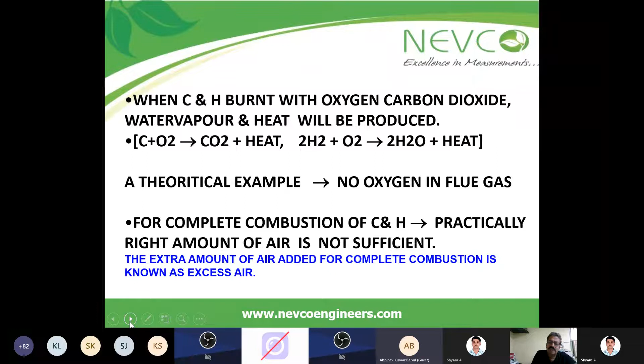To say more about combustion, I still want to give a theoretical example. Combustion takes place when a fuel, most commonly a fossil fuel, reacts with the oxygen in air to produce heat. The heat created by burning the fuel is used in the operation of equipment such as a boiler, hot water generator or any engine. Along with the heat, CO2 and H2O are byproducts of the exothermic reaction. In most combustion processes, some additional chemicals are formed, like CO, NO, NO2, and SO2, and soot. These have to be minimized and accurately measured, because they pollute the atmosphere.